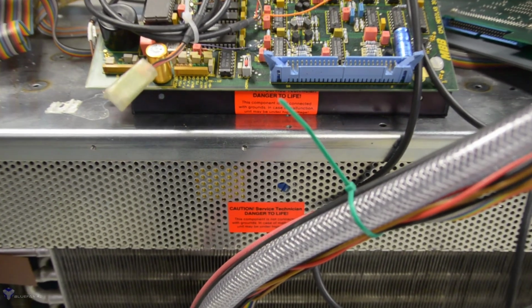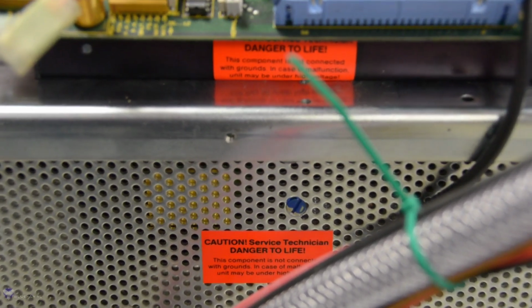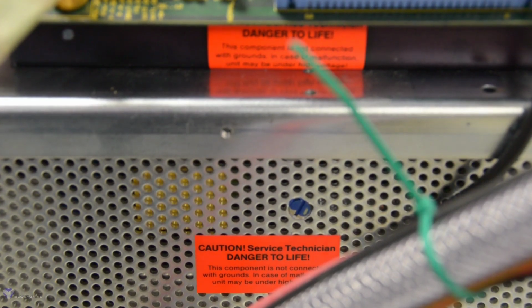I found several of these red warning labels around the laser, and they tell you that the components that the label is attached to are not connected to the mains ground, and that if a fault develops in the unit, they can be under high voltage. Now, I guess the reason why they want to float these units is that switch mode power supplies, and especially a high power one like this arc lamp power supply, can be quite noisy, and dumping that noise onto the mains earth in a hospital environment may not be such a good idea. So all these components are mounted on insulated standoffs.